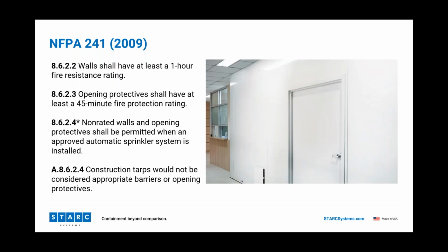So you can either do a 1 hour wall separating the occupied portion of the building from the construction area, or you can do a non-rated wall, but you have to have an approved automatic sprinkler system. This is not optional. I see this all the time. I was walking a construction site just last week where I asked, okay, where's our 1 hour barrier? Where's our 1 hour wall? We don't have it, right? This is very, very critical because we have a higher combustible load in construction. We have to provide that separation because everything ties back to, of course, the means of egress, right? When we have to evacuate, we're only evacuating a portion of the hospital. We don't evacuate the whole hospital.